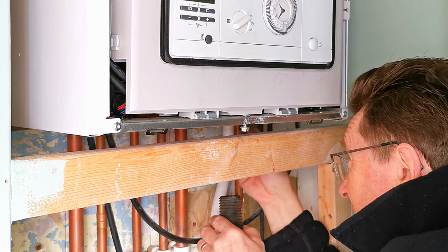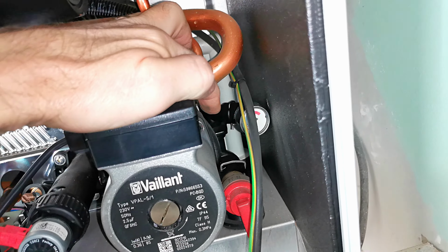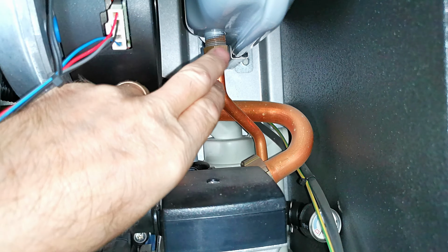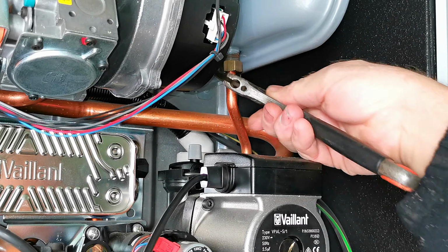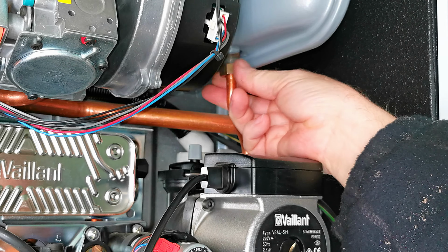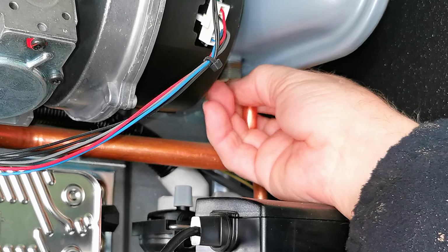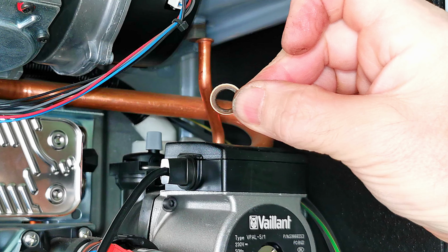I can now remove the wire and close the panel back up again because I don't want any water getting onto that circuit board. The next thing I'm going to do is just to pull out this retainer clip here like that. I'm going to need to disconnect the pressure relief valve, that's the red thing, undo this nut here on the return pipe, remove the pressure gauge and remove the pipe from the pressure vessel. So I'm going to undo this nut here on the expansion pipe which is connected onto the pressure vessel. And there we go, and I'm also going to remove this old fibre washer.